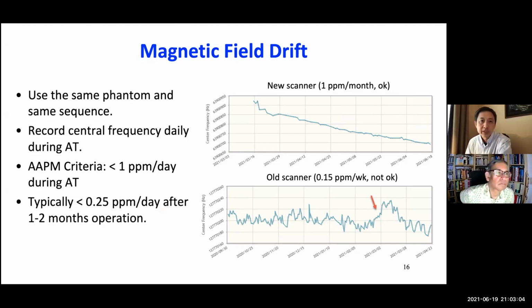The first topic is main magnetic field. Main magnetic field, this is to monitor the drift over time. Like I mentioned, we just put a phantom in the scanner and then scan, then we record the central frequency, okay? But the critical thing is we want to monitor the change. So we have to use the same phantom and the same sequence and the same setup every day or every week, okay? In our case, since we scan the ACR phantom every day, we just use that. So we record the center frequency every day.